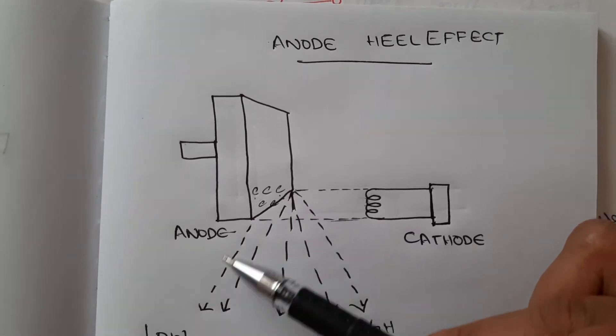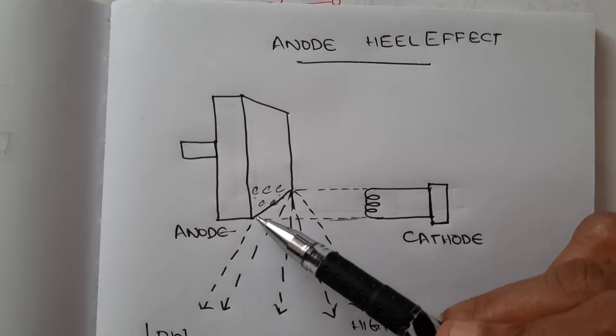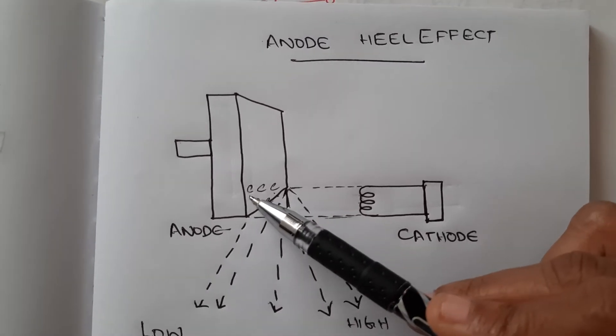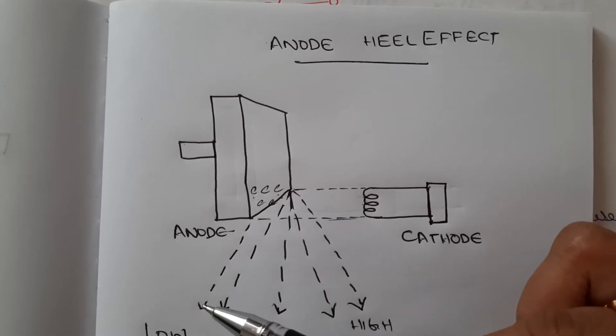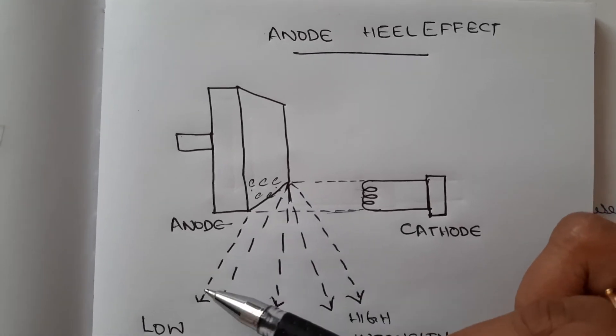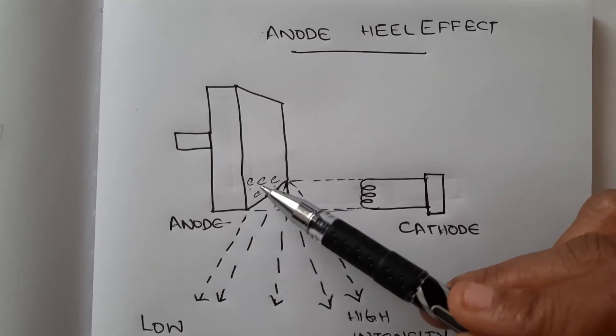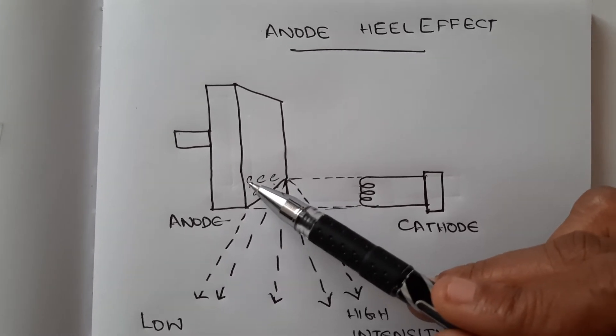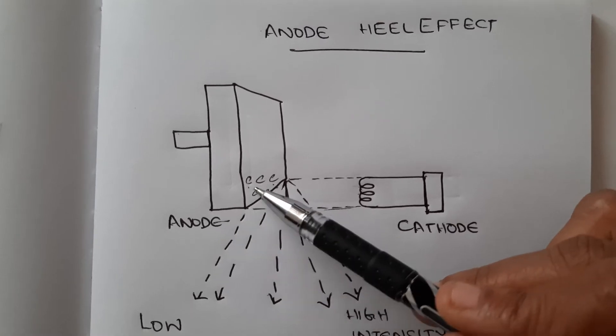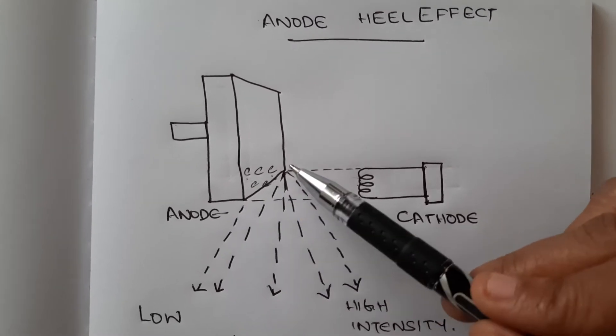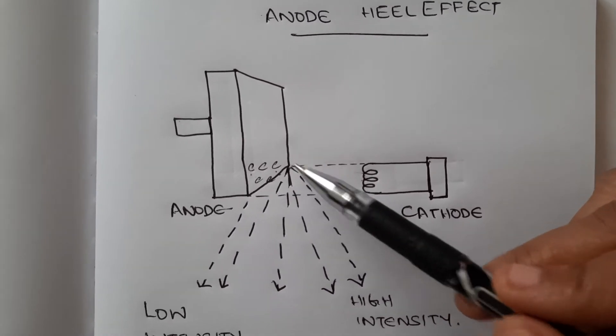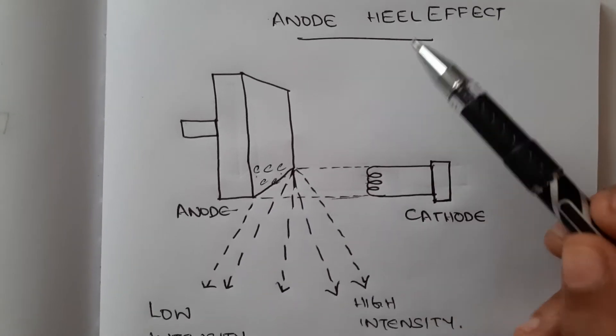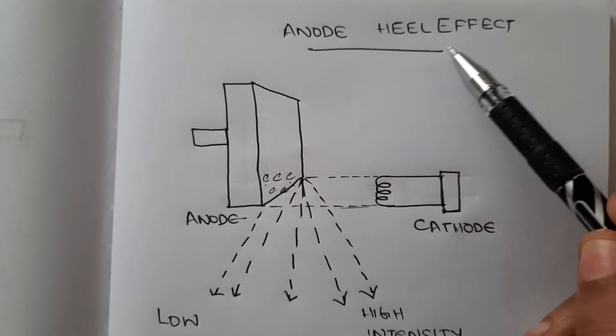The x-ray photons we get towards the anode are due to electrons that are more deeply absorbed. Their intensity is reduced as a result of absorption of a certain amount of energy by the target, compared to electrons that produce x-rays towards the cathode side. This causes the effect known as the anode heel effect.